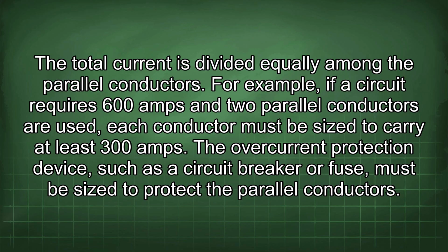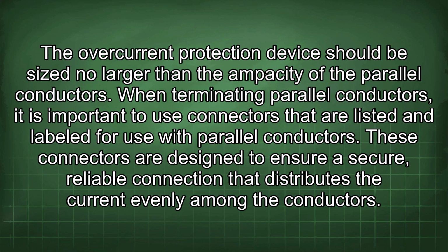The overcurrent protection device, such as a circuit breaker or fuse, must be sized to protect the parallel conductors. The overcurrent protection device should be sized no larger than the ampacity of the parallel conductors. When terminating parallel conductors, it is important to use connectors that are listed and labeled for use with parallel conductors. These connectors are designed to ensure a secure, reliable connection that distributes the current evenly among the conductors.